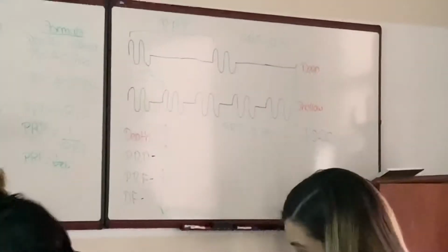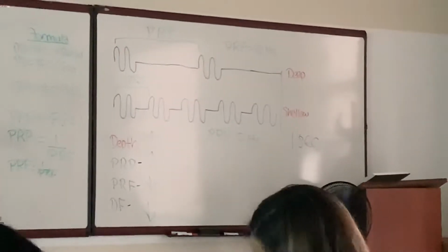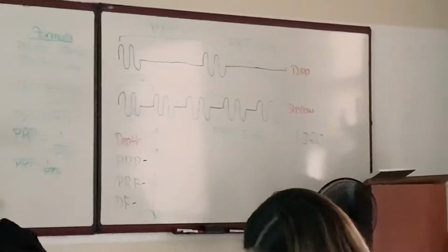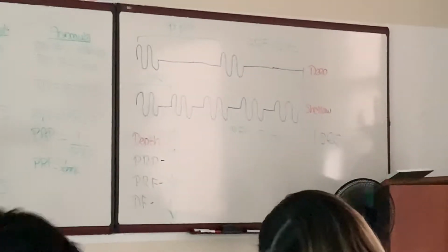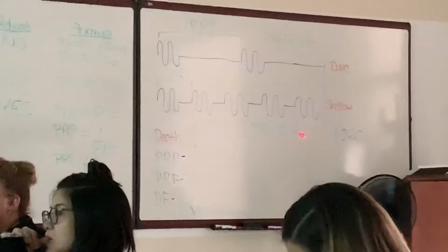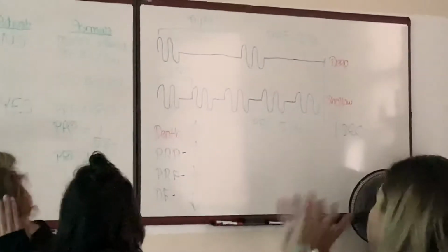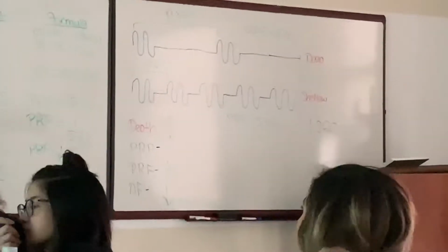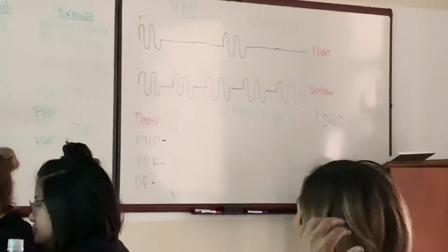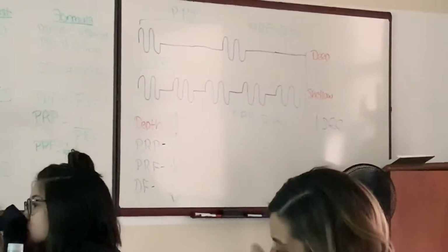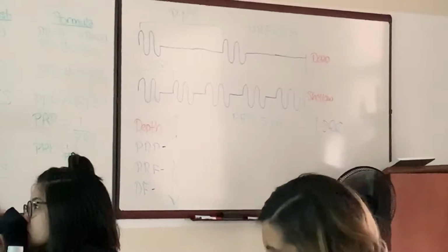Right? If I'm not sending out pulses as frequently, then the machine's not working as often. Okay? So at shallow depths, our duty factor is high. See right here, at shallow depth, our duty factor is high because it's able to transmit more pulses. Okay? When we're deep, our duty factor is low because the machine's not working as hard. It's not transmitting as many pulses.